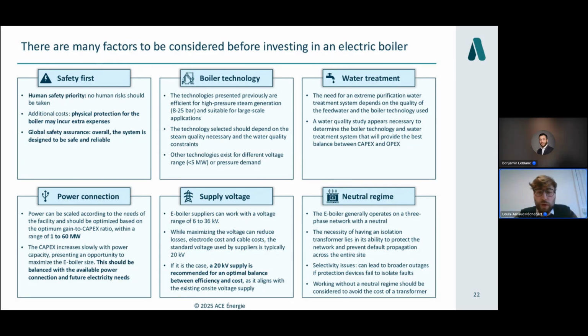Regarding supply voltage, e-boilers can work from 6 to 36 kilovolts. What we recommend is to work with the voltage you already have on site, usually 20 kilovolts, which is the typical value.